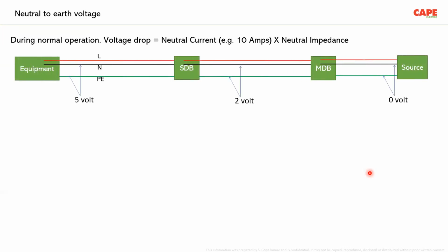Now, the next subject, neutral to earth voltage. All of you know very well that, especially in industry, electronic engineers always say that a neutral to earth voltage of more than 1 volt, more than 2 volt, more than 5 volt is a problem, and we need to reduce the voltage, otherwise the electronics are failing and so on. What is this neutral to earth voltage? I'm just showing a simple circuit.